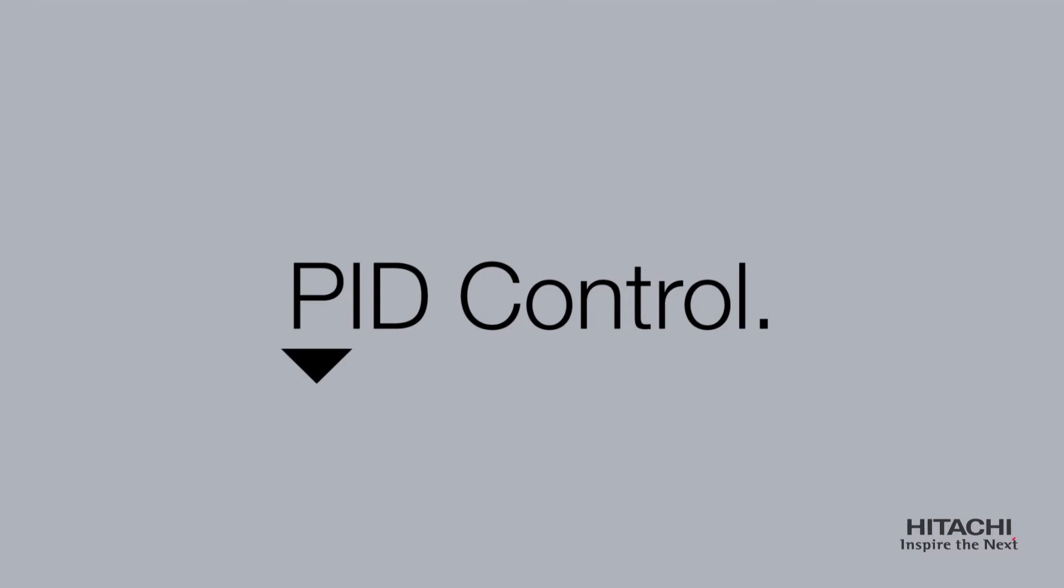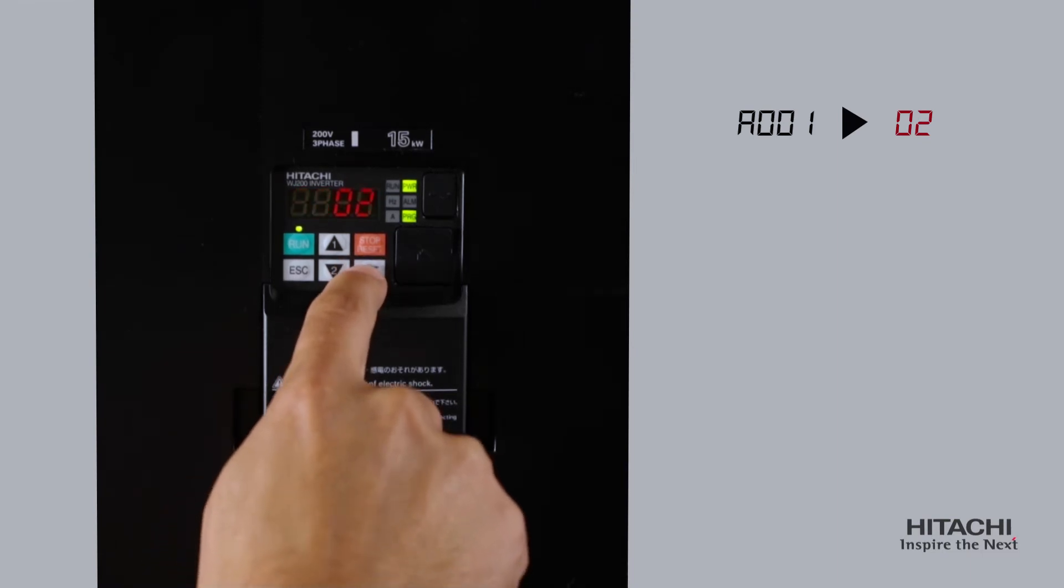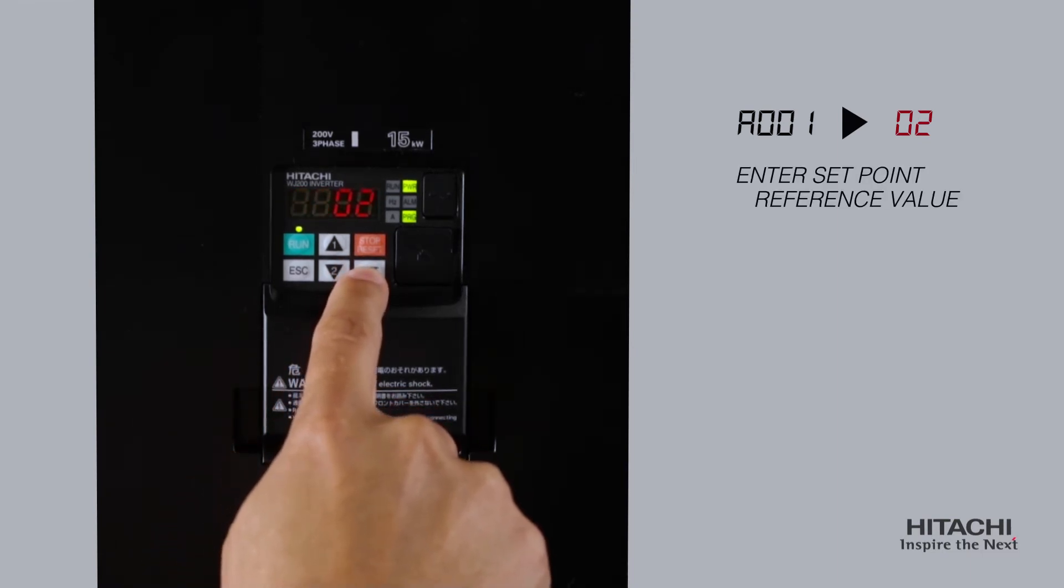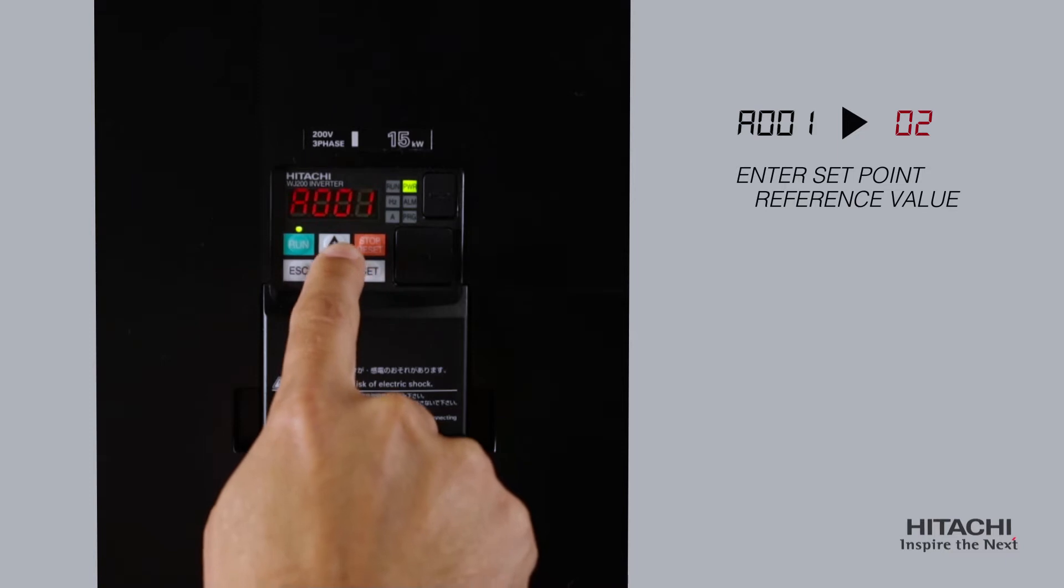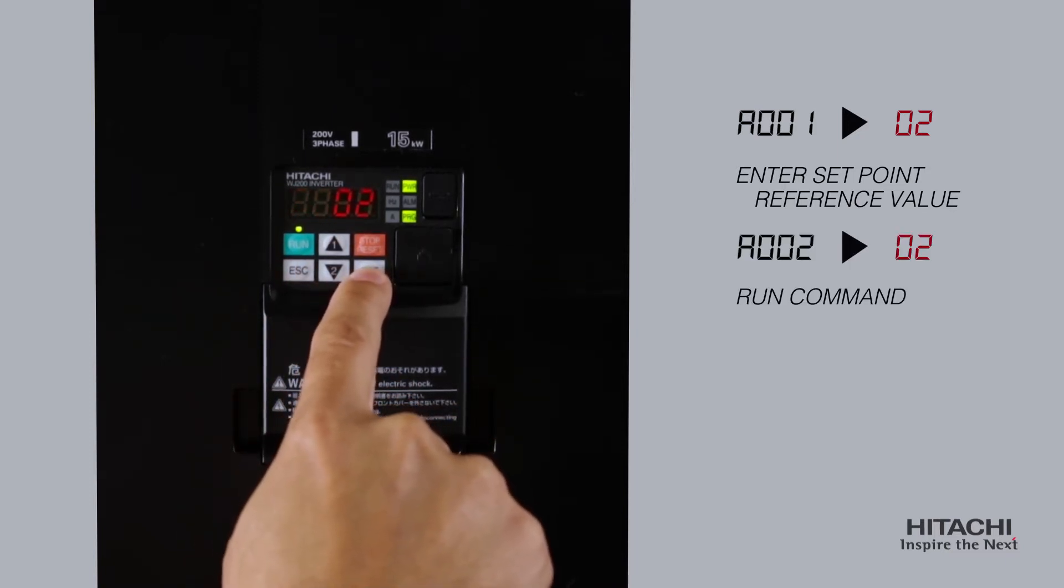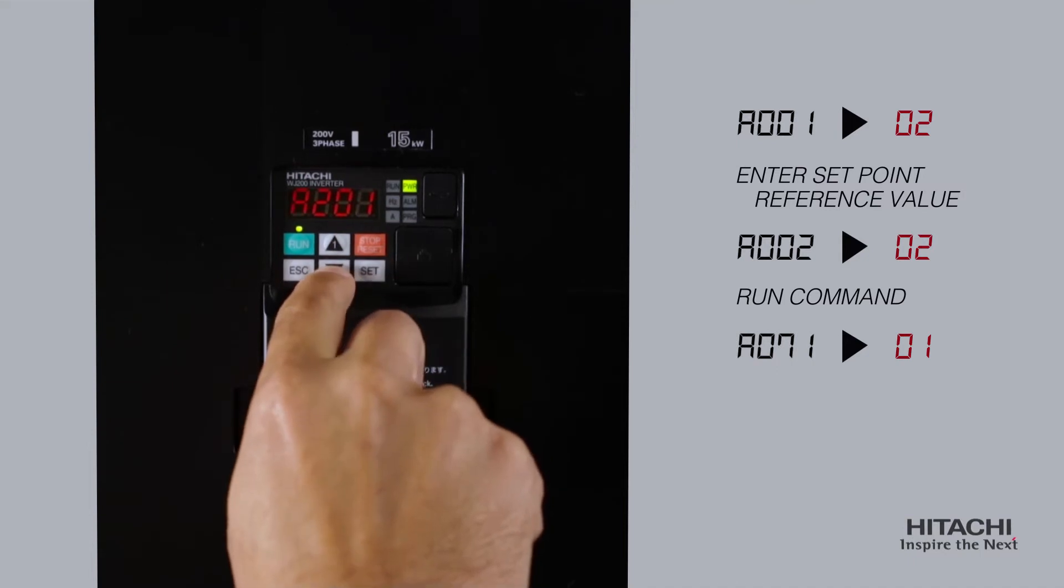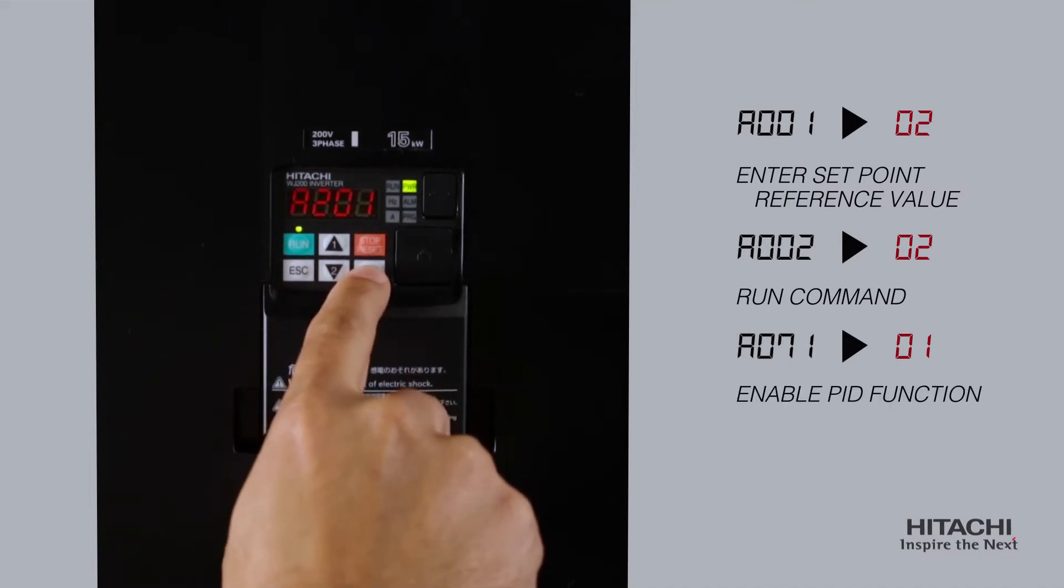PID control is a popular method to maintain a set pressure point. Set A001 to 02 and enter the set point reference value. Set A002 to 02. This is the run command. Then set A71 to 01 to enable the PID function.